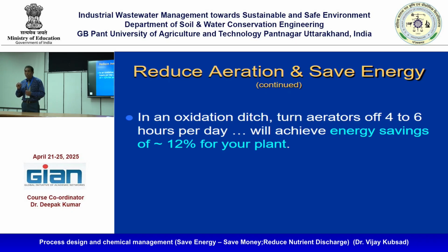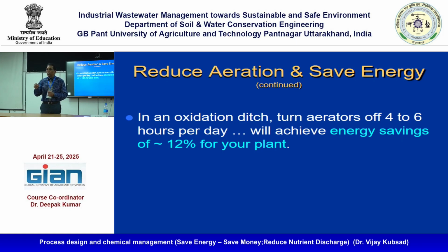What will you do? You will see whether that contaminant concentration exists in the sludge, because you remove and recycle 40 to 60% of the sludge. Then you analyze whether it is just depositing in the sludge and you are transferring the same. So how is a different direction possible? Because we have worked in the field, we know why it fails. If I say 40% should be recycled, see that this is being achieved.